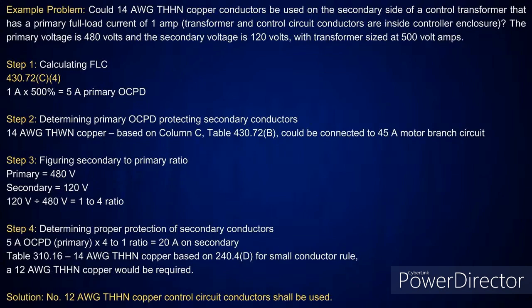This is your transformer control circuit. Conductors are inside the control enclosure. The primary voltage is 480 volts and the secondary voltage is 120 volts, with transformers sized at 500 volt-amps. So I'm going to take the 1 amp at 500%, and that's going to give me what? A 5 amp overcurrent device.